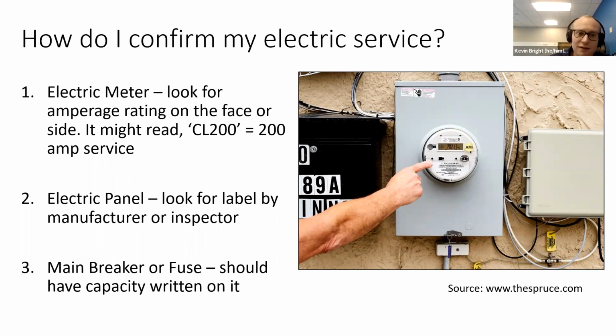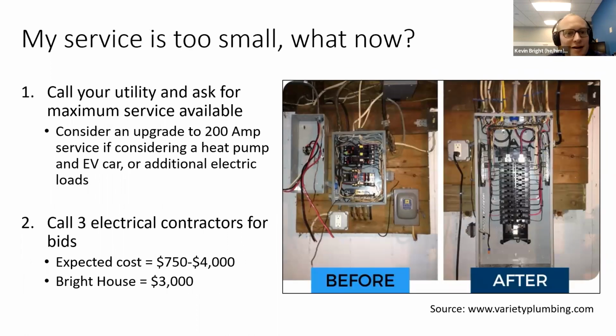Let's say you go down and look, and it's only 100 amp service—what do you do next? First, call your utility to figure out the maximum service available to your house, and consider upgrading to 200 amp service. It probably won't be necessary just for integrating a heat pump—if you have 100 amp service, 150 amps would probably be plenty, depending on the unit. But if you also want to electrify other energy loads, like converting your gas stove to electric, or you're thinking about an electric car in the future, it's worth asking what the maximum available service is—probably looking at 200 amp service would be great.